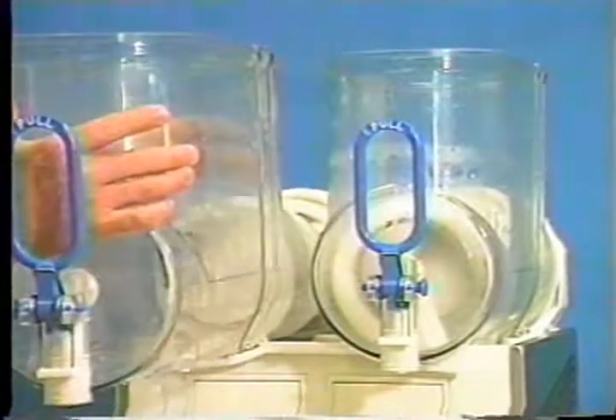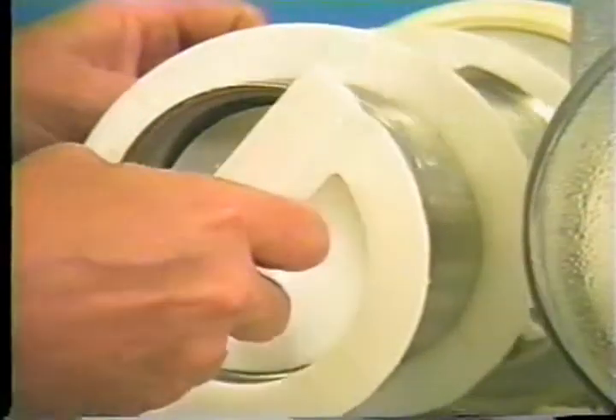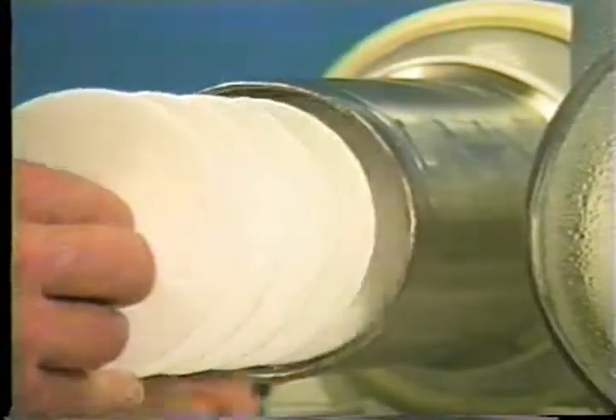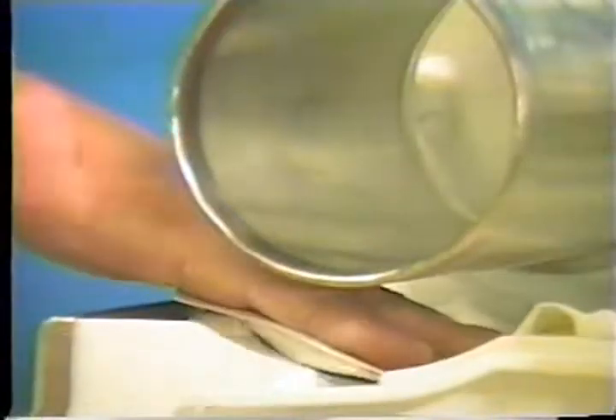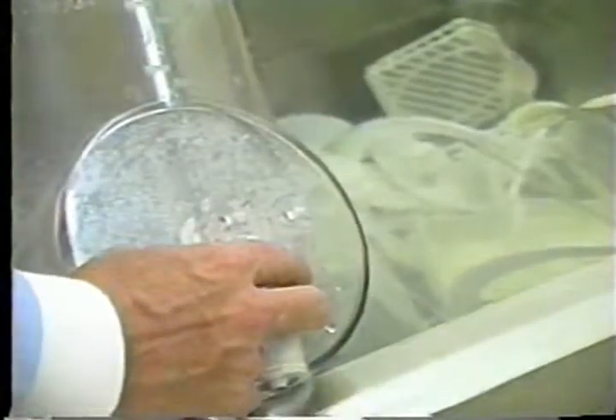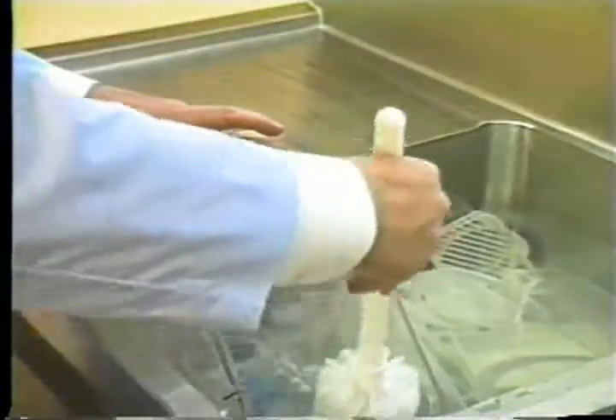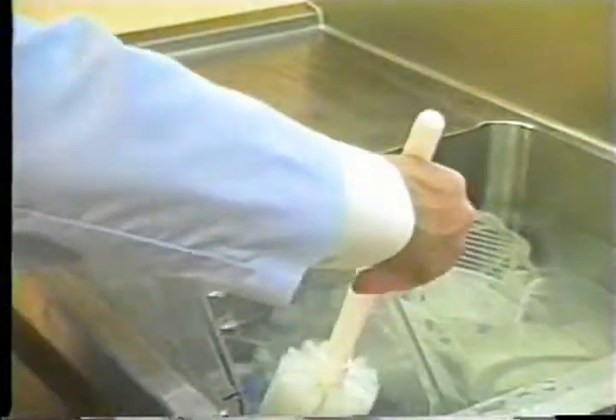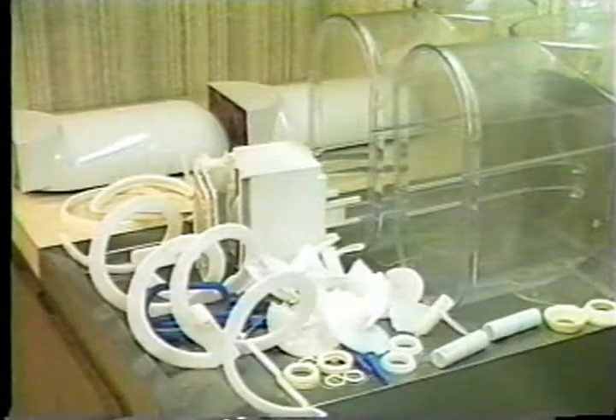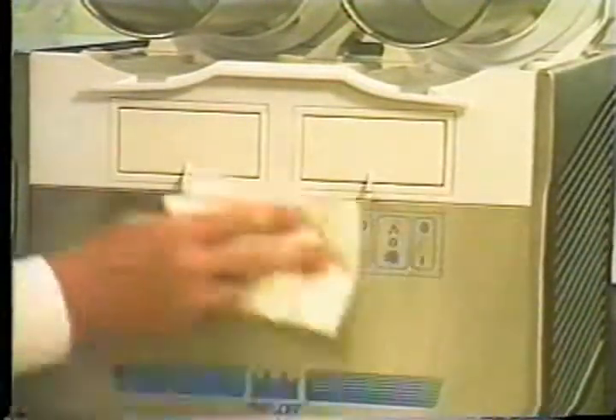Be sure all switches are in the off position. Remove the hopper, outer spiral scraper blade, rear hopper gasket, and beater shaft and beater shaft seal. Take these parts to the sink for cleaning. Wipe any excess liquid from beneath the evaporator using a single service towel. Prepare a sink with an approved cleaning solution in warm water. Completely disassemble all components including O-rings, seals, and gaskets. Thoroughly brush clean all disassembled parts in the cleaning solution, making sure all lubricant and mix film is removed. Place all the clean parts on a clean dry surface to air dry. Wipe clean all exterior surfaces of the freezer.